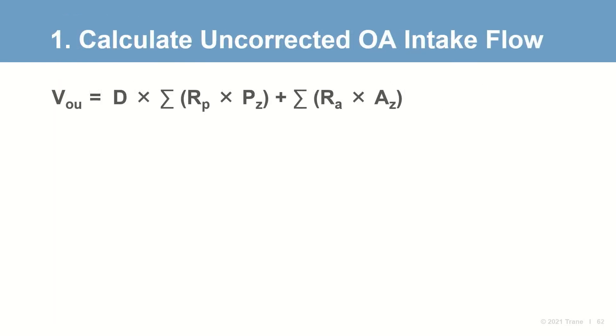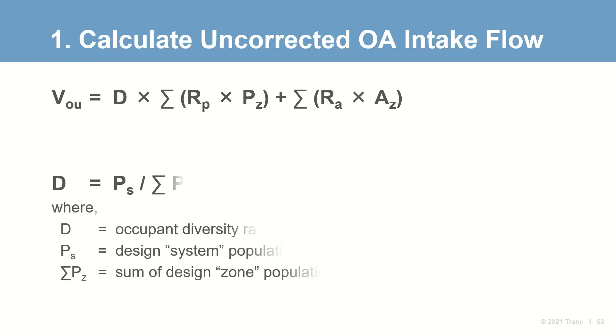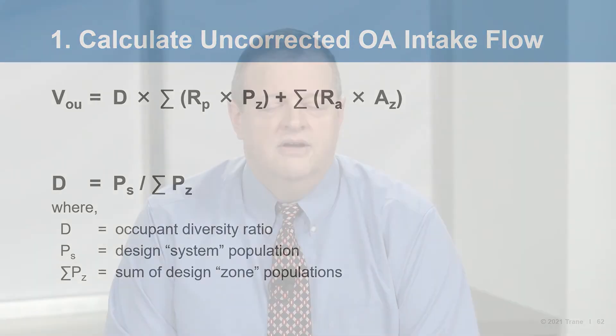For step one, the equation for V-sub-OU is basically the sum of the breathing zone ventilation rates, with one addition: a factor D, the Occupant Diversity Ratio, multiplied by the people-based component of the ventilation rate. Mathematically, it's the ratio of the expected design system population divided by the sum of the design populations for all zones. For example, in our office building, a person is expected to be in their office or cubicle, or in a conference room — not both zones simultaneously.